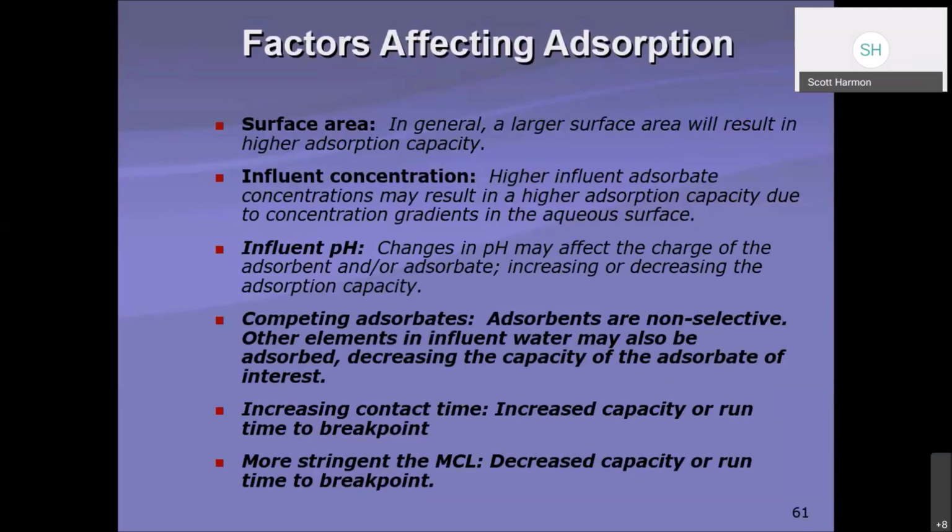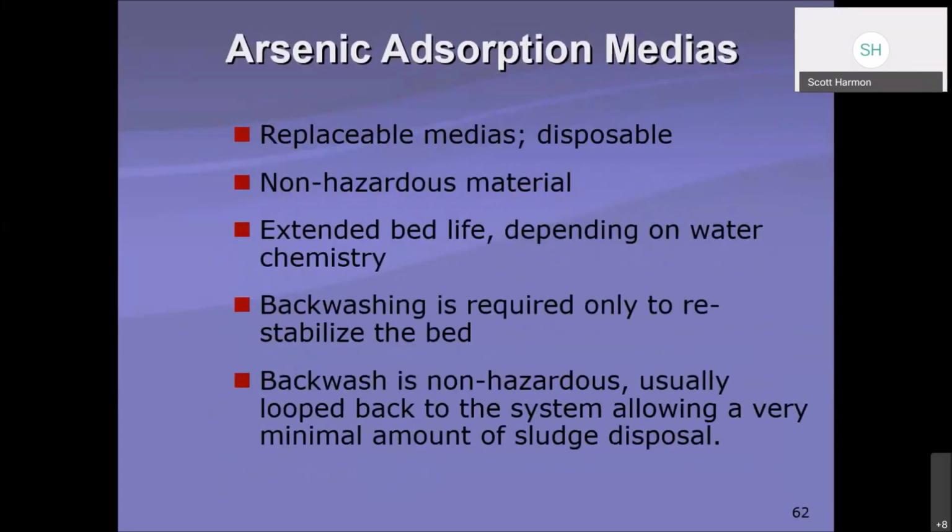Increasing contact time increases capacity, or run time to breakpoint. So that's typical filter speak. A more stringent MCL decreases capacity or run time to breakpoint. So if the MCL lowers, that could be an issue for the type of media you're using, or the size and shapes of your filters.